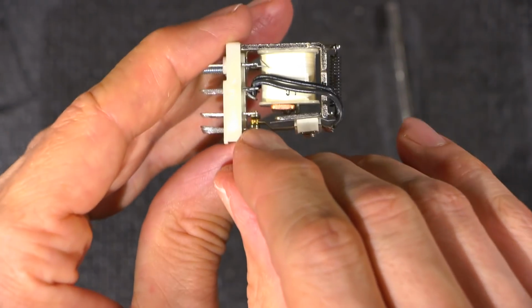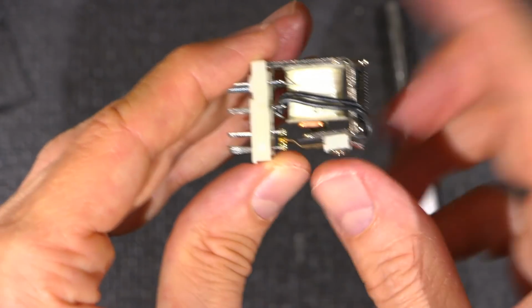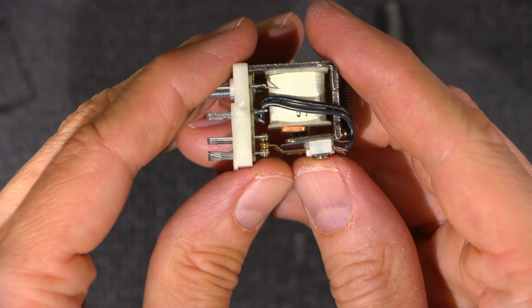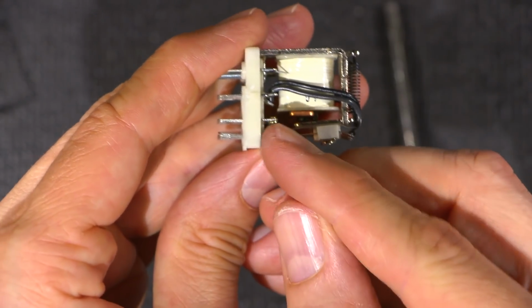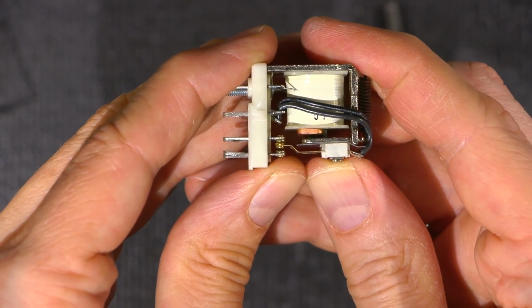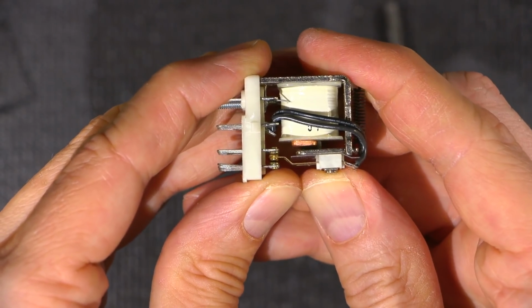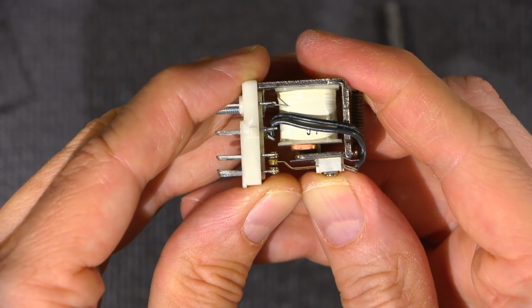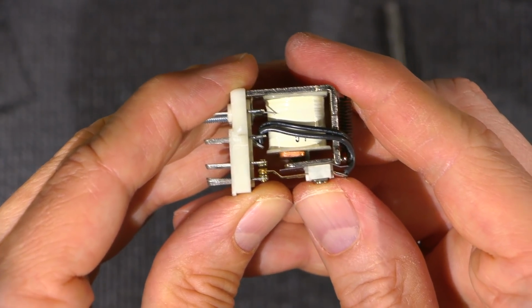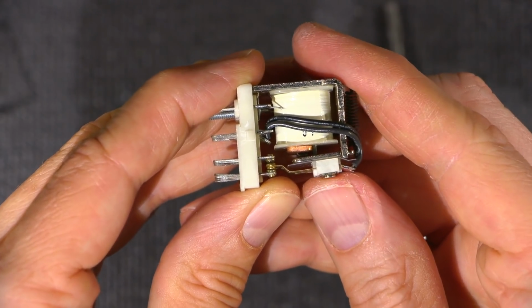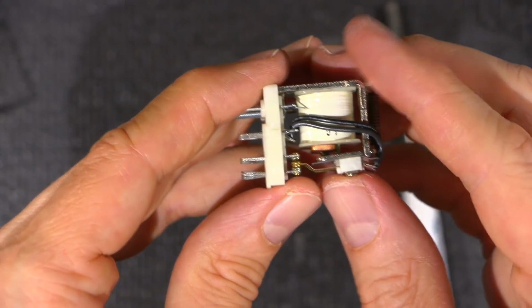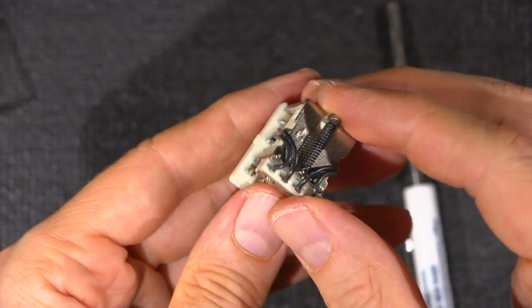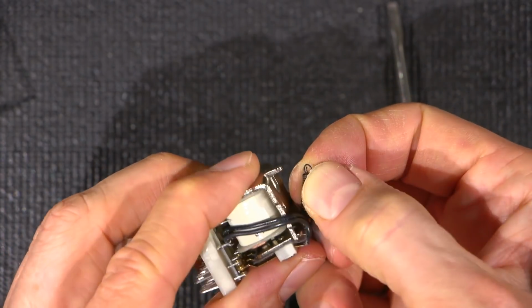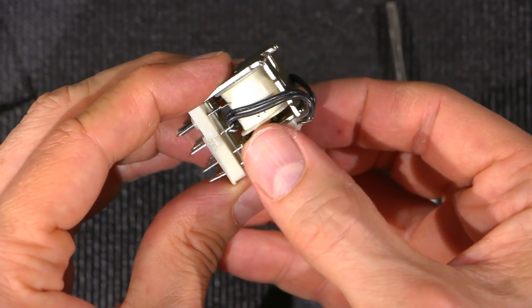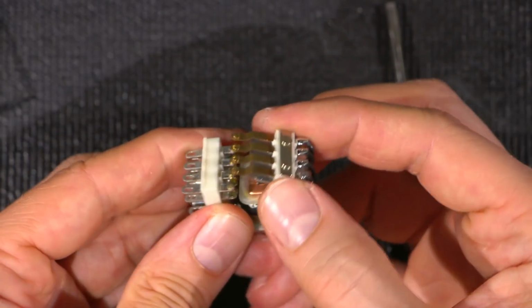And you'll also notice that it creates a scrubbing type of motion on the contact to stop them from welding as well. All of these things were taken into consideration when they designed these relays. So if you watch this contact, you'll actually see it rub downwards. See how it's kind of rubbing downwards as it's making contact? That's to clean the contacts. And it's the same kind of thing on this side. It's touching, but if I let it go, you see how it pulls up? So it has a scrubbing motion, and they're using that as well as for tension reasons to make sure the contact is good. Now, getting something like this apart is relatively easy. Use eye protection as you're doing this, because a lot of the time these things will take off. Make sure it doesn't. All you do is unclip this spring like so, and on the top, this pulls out, and you can take the whole thing apart just like that.